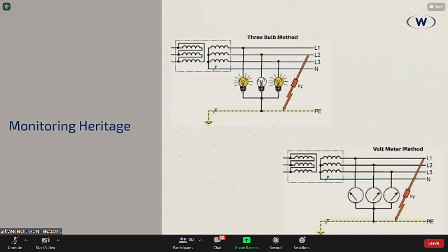this old method, that's why we call it heritage. Now, this old method was great for pure sinusoidal AC systems. But now, when you have active harmonic filters, you have capacitor banks with reactors, you have variable frequency drives, you have inverter TVs, you have a hell lot of computers, you have a lot of nonlinear loads, LED lights and devices, no? Then we also have distortion on that sinusoidal waveform.